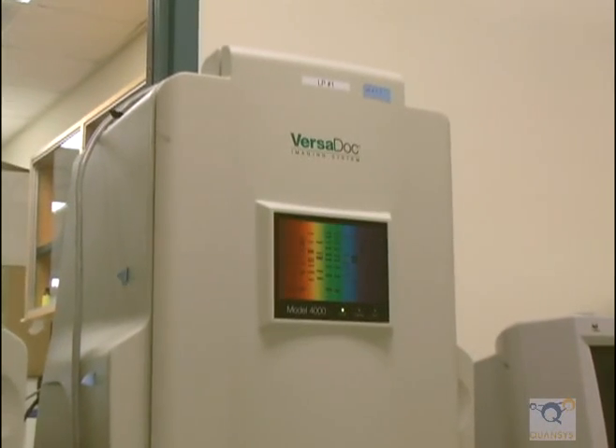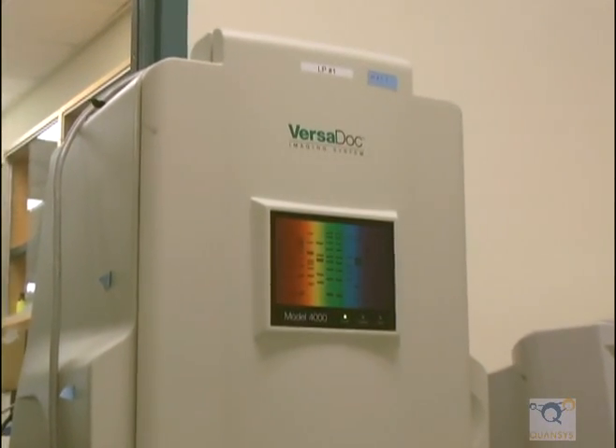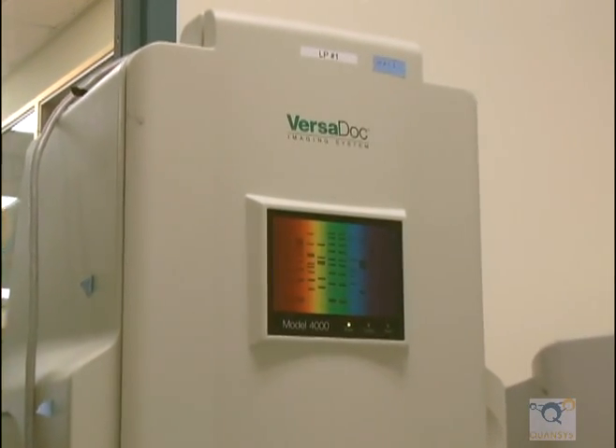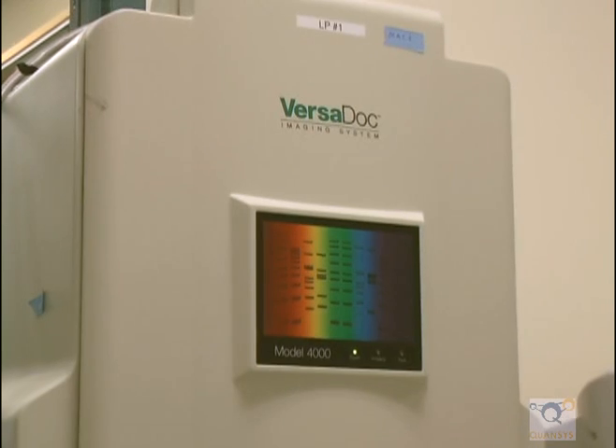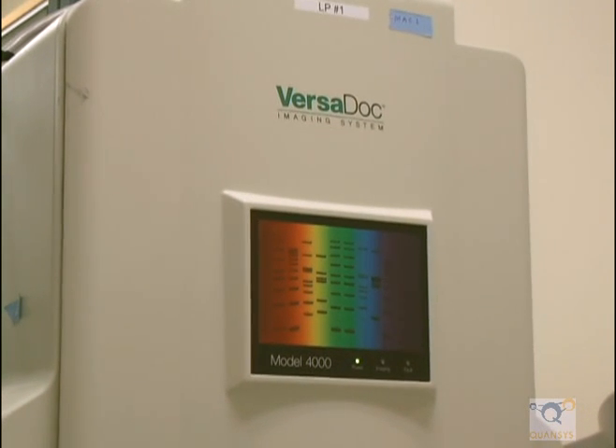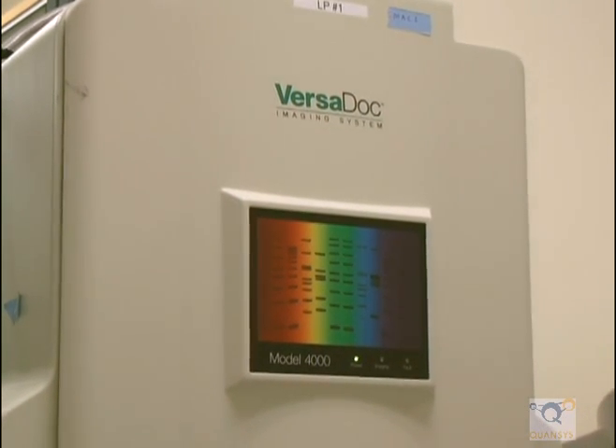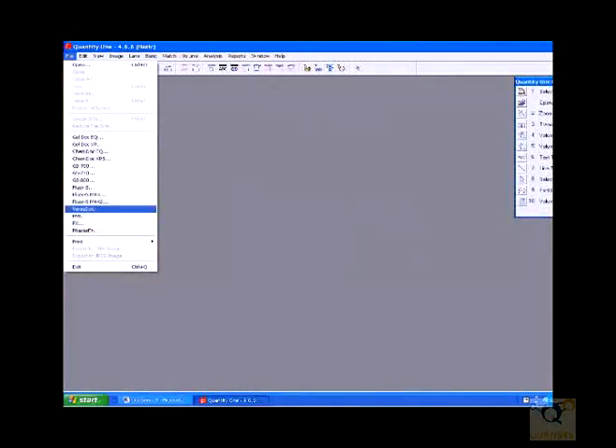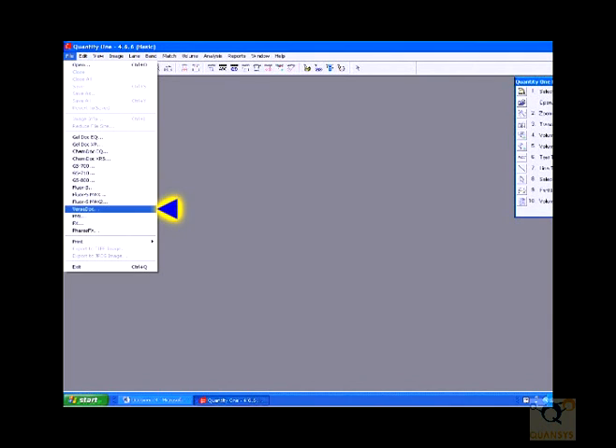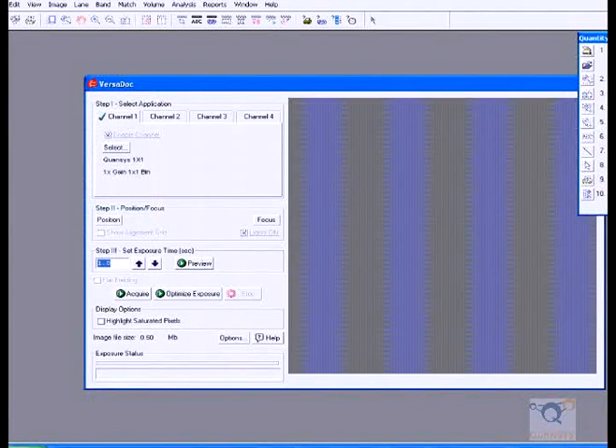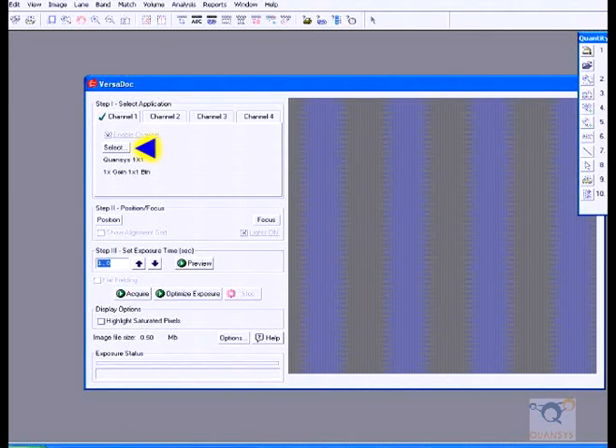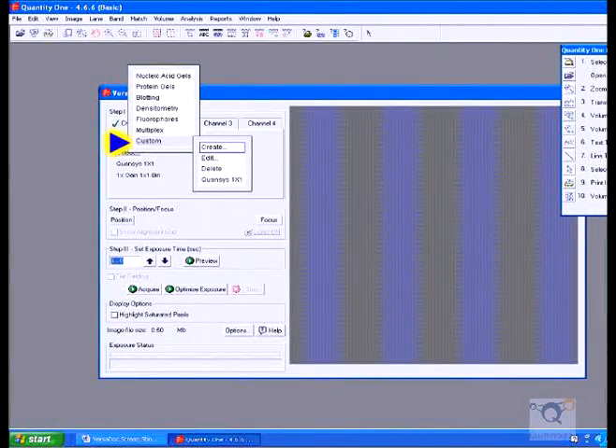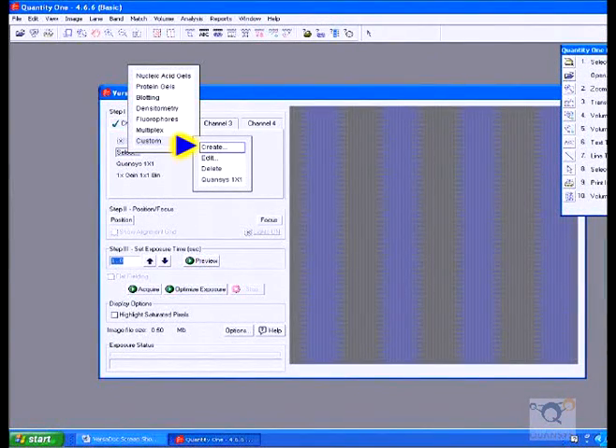Bio-Rad Versadoc Camera and Software Setup for Imaging Quansys Chemiluminescent Multiplexed ELISA. File Setup: Open the software on the computer. Click on File, then select Versadoc. Make sure that only Channel 1 is enabled. Click on the Select button, then select Custom and then Create.